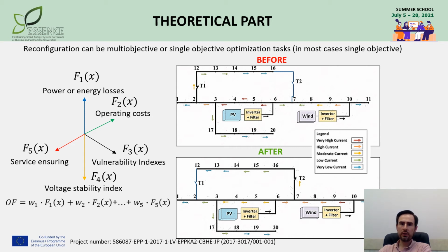The other objective is characterized by vulnerability indexes and shows how close the system is to its operating limits. For a node, this limit is related to the voltage deviation from its nominal or specified value. For a branch, this represents its overload factor. One more factor which can be considered is system-wide allowed frequency deviation from its nominal value. So the smaller the frequency and voltage deviation and the larger the distance from current limit, like shown in the example on the slide, the better. One more objective is also associated with the voltage level: voltage stability index. This index shows how far the actual voltage level is from the minimum one, at which voltage collapse occurs.